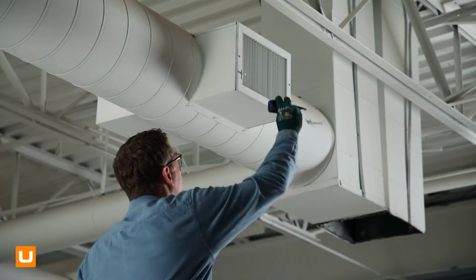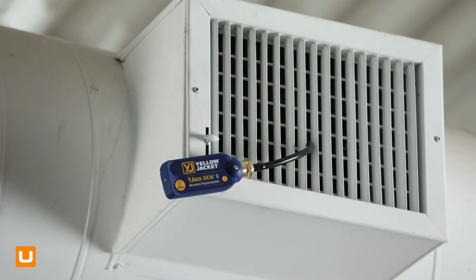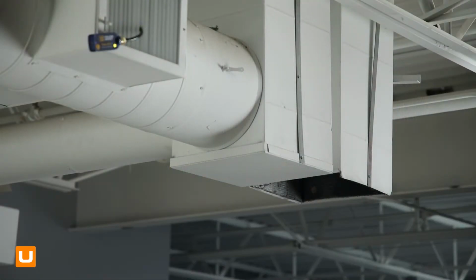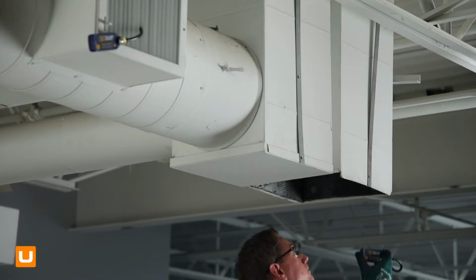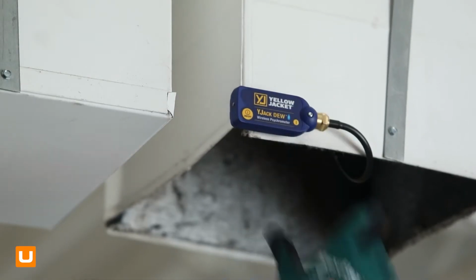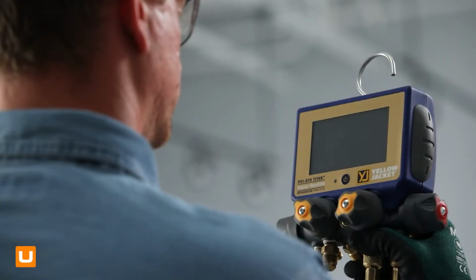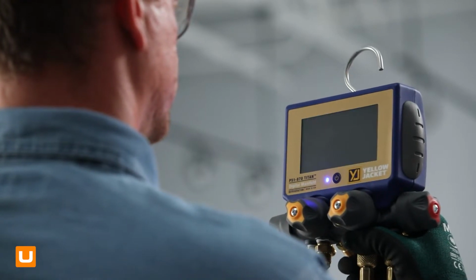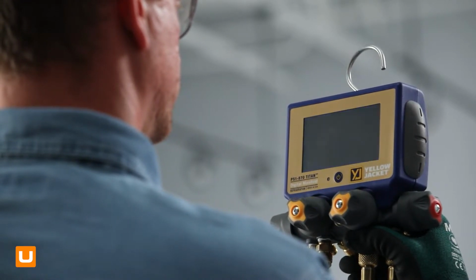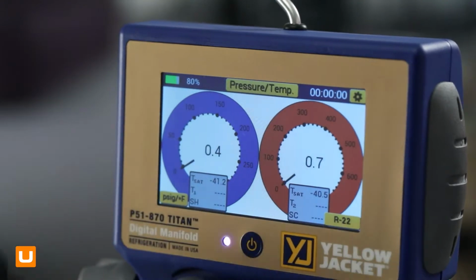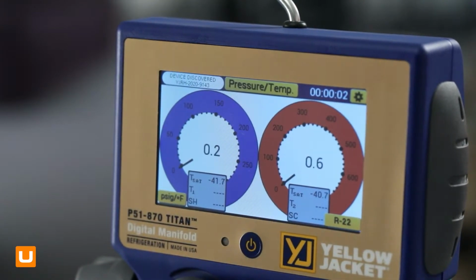We'll place this YJACK psychrometer on the supply air duct. This second YJACK will be placed at the return air side of the unit. With the YJACK probes in place, let's power on the P51 870 Titan digital manifold. Select pressure temperature session. By default, the manifold pressures are displayed.